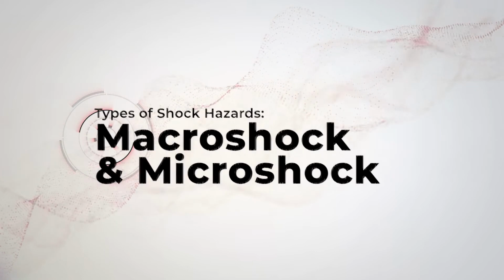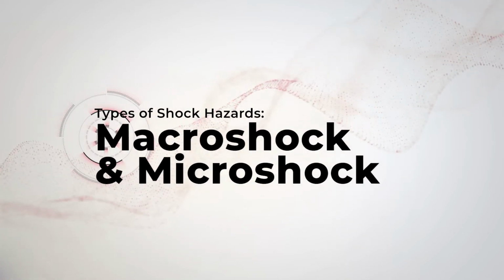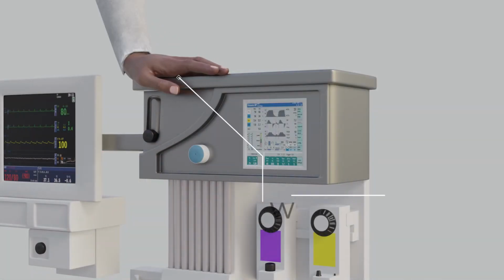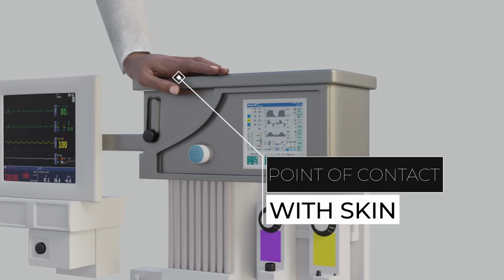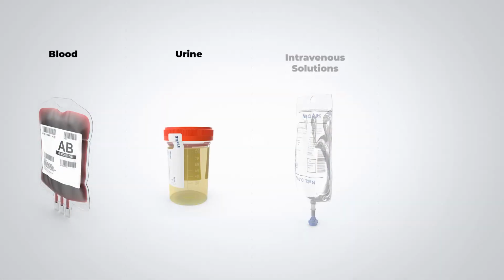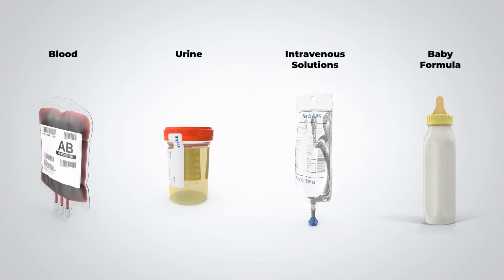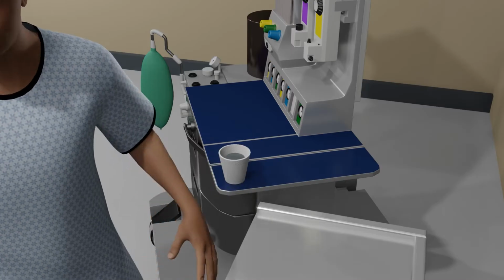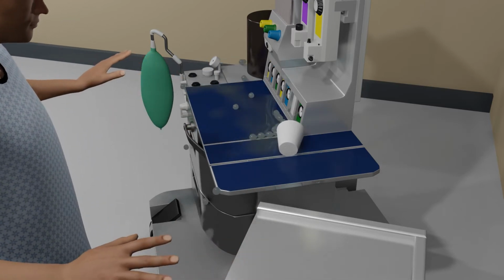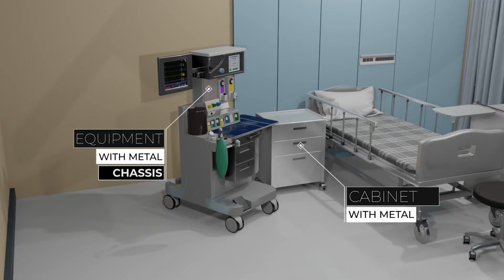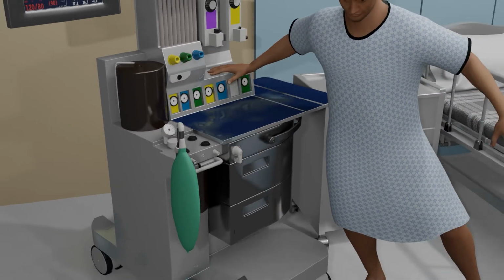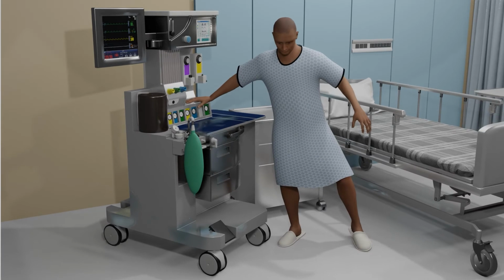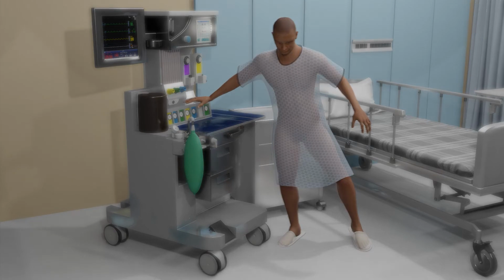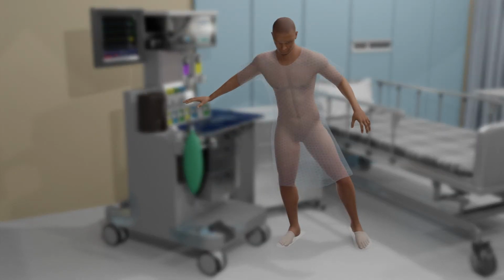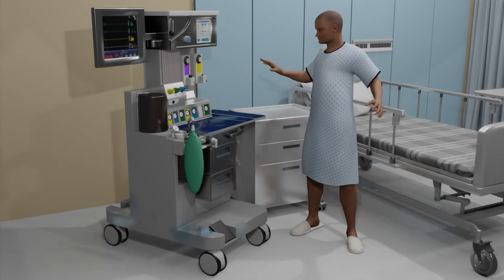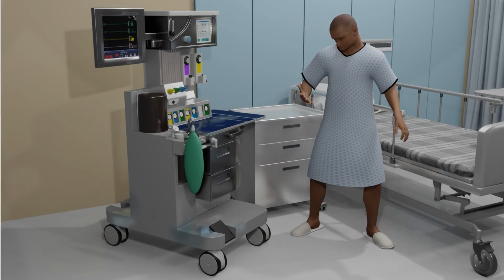There are two types of shock hazards, macroshock and microshock. Macroshock occurs when an externally applied current passes through the body via contact with the skin. Blood, urine, intravenous solutions, and even baby formulas can conduct enough electricity to cause temporary short circuit if accidentally spilled into normally safe equipment. This is especially hazardous in equipment designed with metal chassis and cabinets that patients and staff may touch. If the equipment is ungrounded, the shorted components between the hot power lead and chassis result in 220 volt potential between the chassis and the grounded object. Consequently, touching the chassis and any grounded object simultaneously results in a macroshock.